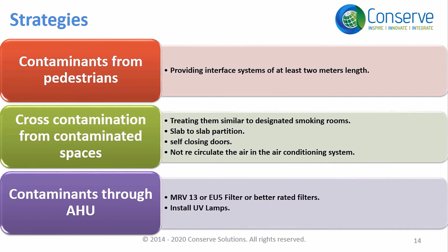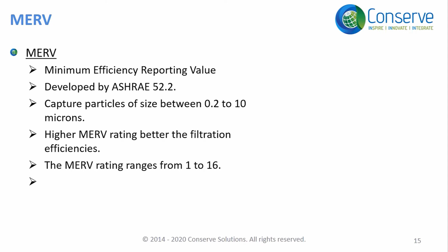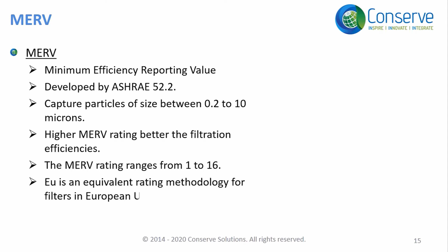MERV is an abbreviation of Minimum Efficiency Reporting Value. MERV is a rating developed by ASHRAE. To be more particular, ASHRAE standard 52.2 to report filters' ability to capture particles of size between 0.2 to 10 microns. Higher the MERV rating, better the filtration efficiencies. The MERV ratings ranges from 1 to 16. EU is an equivalent rating methodology for filters in European Union.